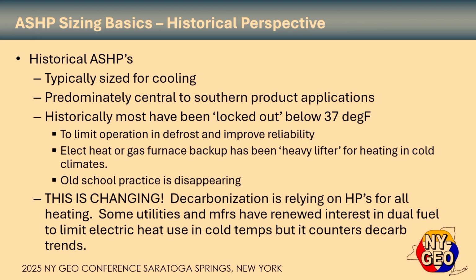So let's talk about air source heat pump sizing basics. Historically, air source heat pumps are typically sized for cooling. It's predominantly central to southern product applications. Those in the north, we haven't really had a lot of heat pump applications over the years. Most of the dealers in the north have kind of steered clear. There's usually been natural gas available, so it's obviously the predominant. But I think you're starting to see more and more air source heat pumps get sold in the north.